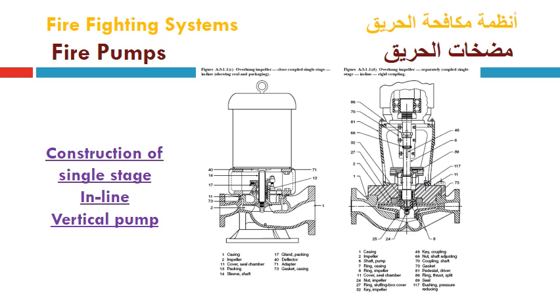This slide also shows the construction of a single stage inline pump in a vertical arrangement with a close coupled motor, and how the motor is affixed to the impeller, and how the suction flange is located here to direct the flow from the suction flange to the impeller eye. Then the impeller discharges the flow in the volute casing and discharges it from the discharge flange, which commonly has a smaller diameter than the suction flange.